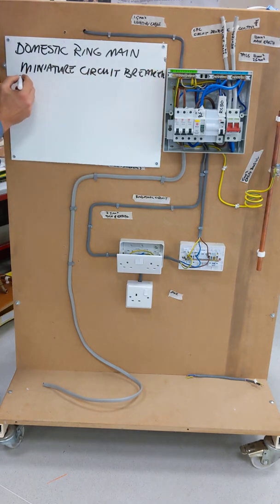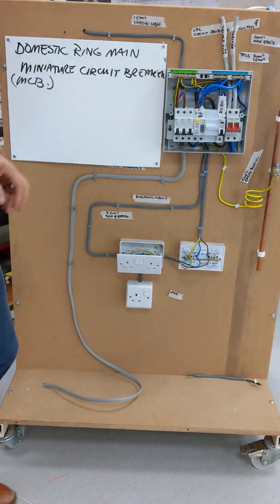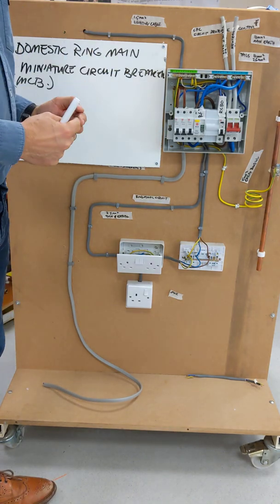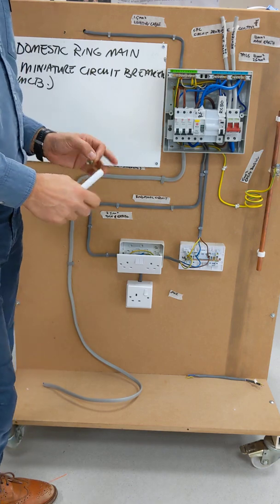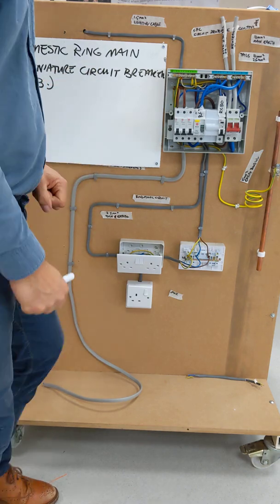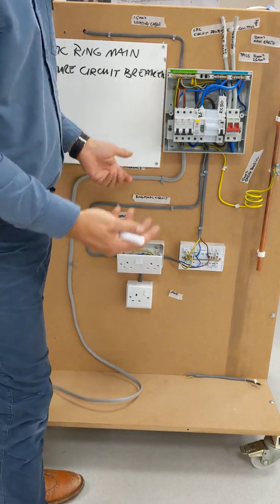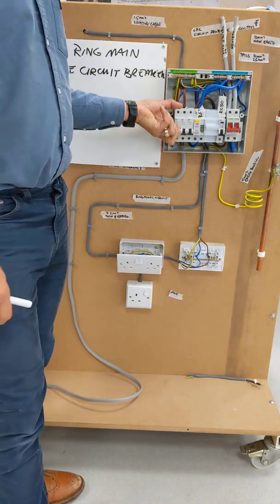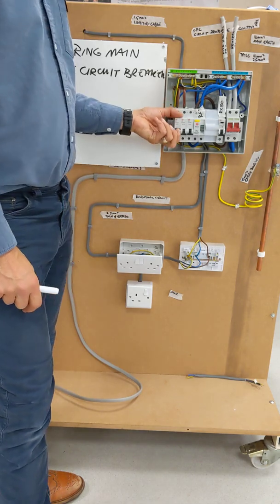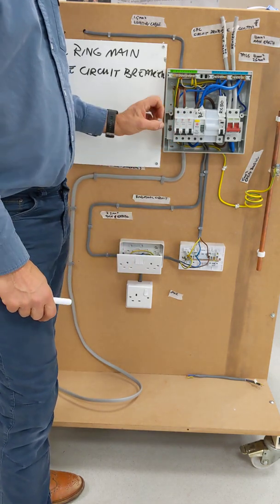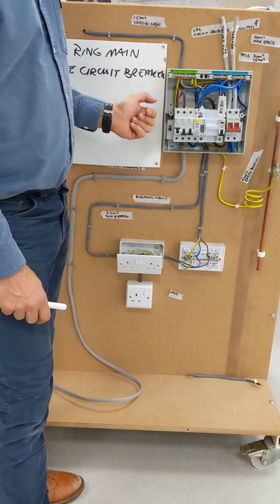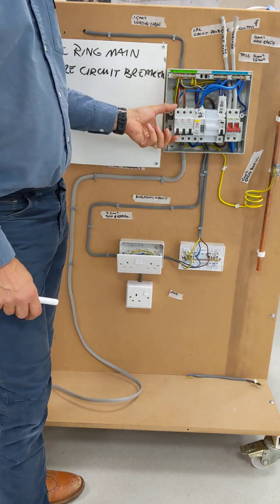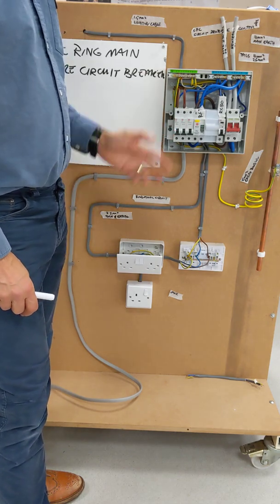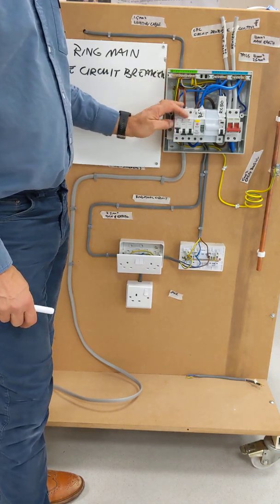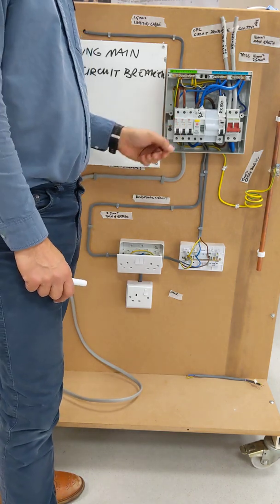Now, a miniature circuit breaker, MCB, right, is a device that is a bit like a fuse, really. And a fuse will blow, so it's basically a thin piece of wire which is rated to a certain current. If over that current is sent through, the wire heats up and melts quite quickly. Well, an MCB is like a resettable fuse, basically. With too much current flowing due to a fault or something happening in a device, the current will overload and trip the MCB, the miniature circuit breaker. It trips and your power will cut off, and then you fix the fault, and if it goes back up again into the on position and stays on, then you know you're safe to use the appliance.